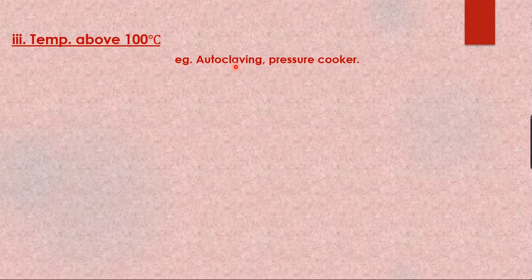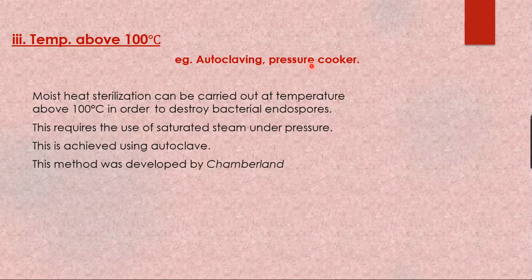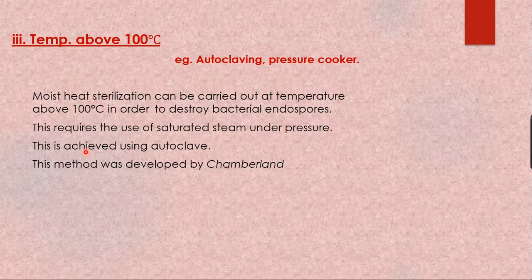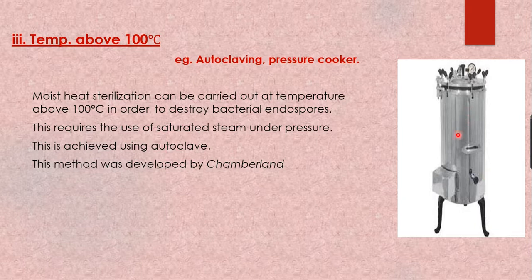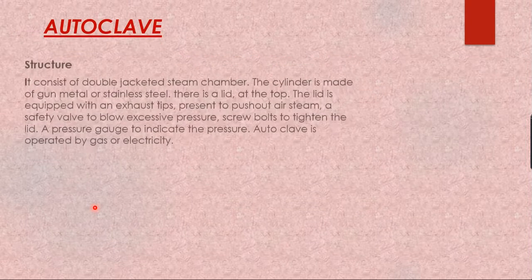The third method is temperature above 100°C, also called steam under pressure. Moist heat sterilization carried out above 100°C can destroy bacterial endospores, but this requires the use of saturated steam under pressure. This is achieved using equipment called an autoclave, and the process is called autoclaving. This method was developed by Chamberland. In the laboratory we have different types of autoclaves — here is a vertical type, which has a pressure gauge and double walls.